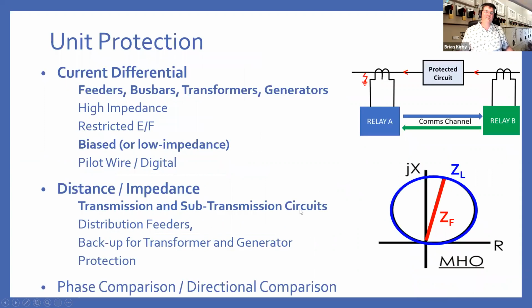So if we look at unit protection, the two most commonly used methods of unit protection are differential and impedance or distance based. In differential protection, you have a circuit you're protecting and you have measurements either side of it. So long as the current flowing in and flowing out of your circuit is roughly the same, allowing for measurement errors, you would say that your circuit is healthy, and anything that happens outside, you're not going to respond to. Feeders, bus bars, transformers, generators, all of them have their own versions of differential that can be applied. You can even do things like vector compensation for transformer shifts and things like that.